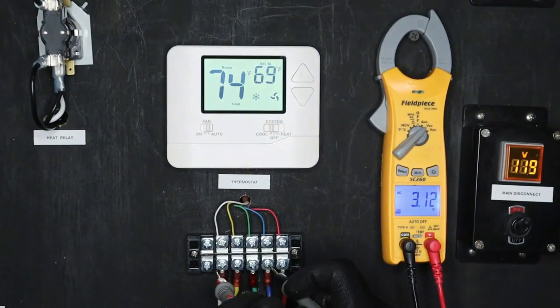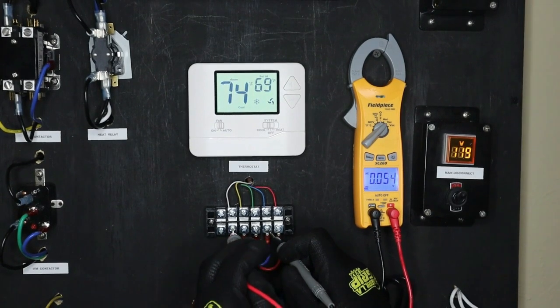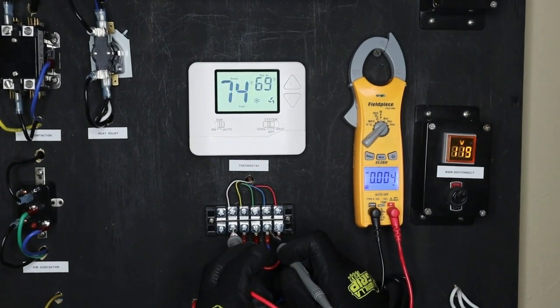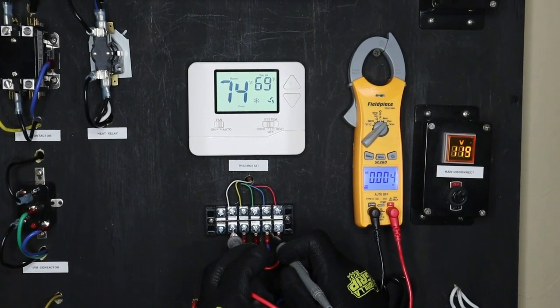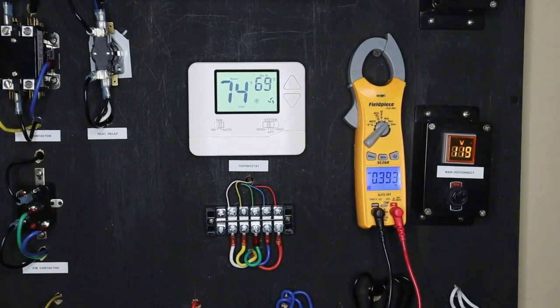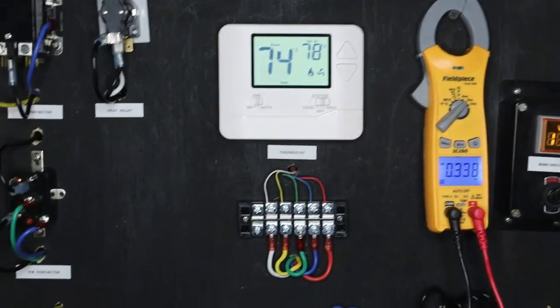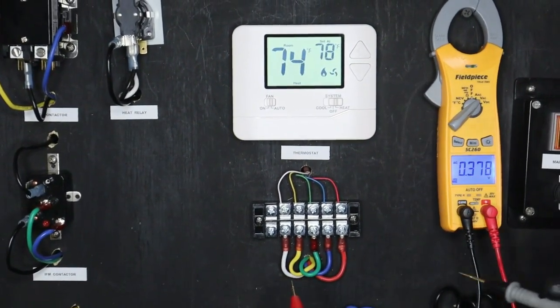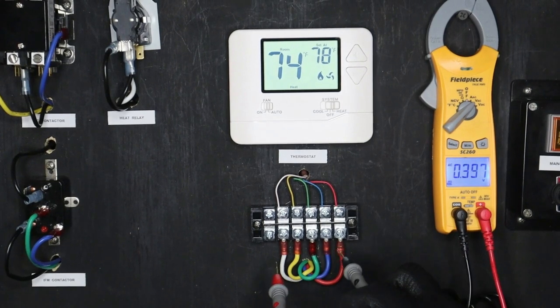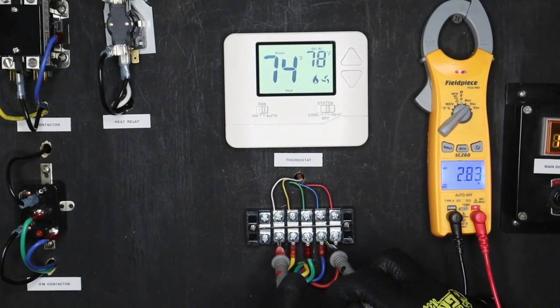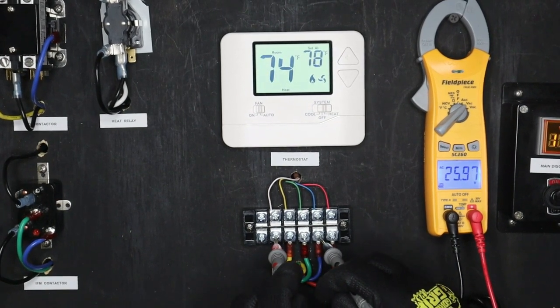Now the heat is off so if I should measure across the heat terminal of my thermostat I should have zero volts. As you can see I have 0.004 volts so that is not energized. Now if I should turn the heat on it has an on-delay, so currently if I measure it I have 24 volts, 25 volts, now it's energized.